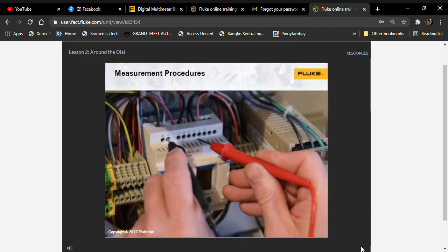The order that the test leads are touched to or disconnected from an energized circuit is a safety rule. It's best to minimize the time that a multimeter is connected to ungrounded or hot conductors. The red test lead, when touching ungrounded conductors, should be connected last and disconnected first. It's not necessary to do this when measuring de-energized circuits or components, but it's still a good habit to have.